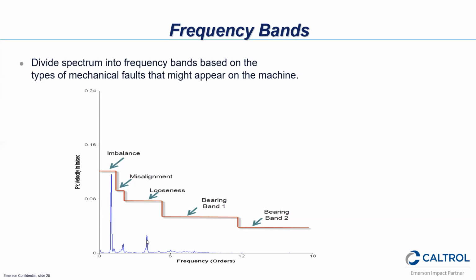When you're just using an overall pen, what that's doing is taking this amplitude number here, combining all of these frequencies together and giving you an overall number. Now we use that overall number too, because that's part of our trend for seeing a change when that overall goes up. But when we use an FFT analyzer, we break it down into different bands. We have probably 10 different bands of vibration data, and within those bands, each thing that happens there represents a different fault in the asset. It's part of our analysis.